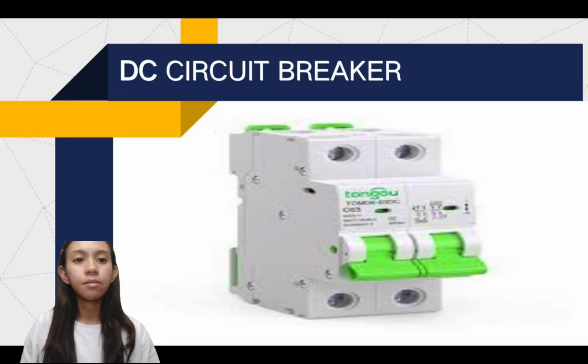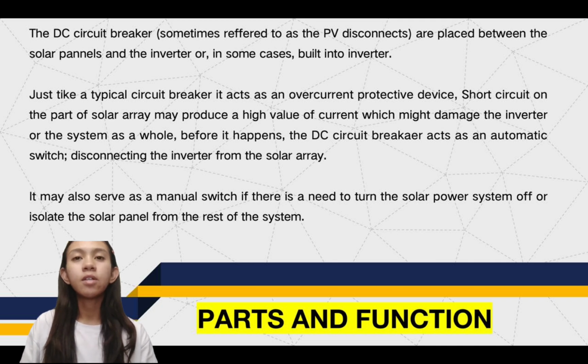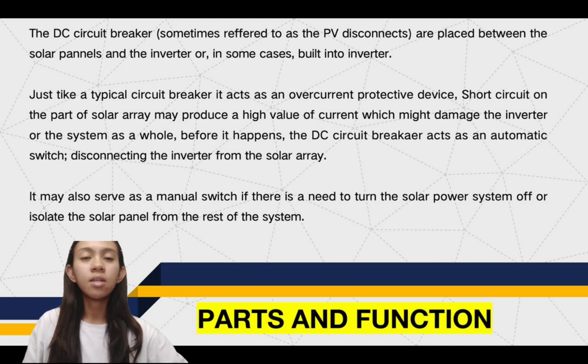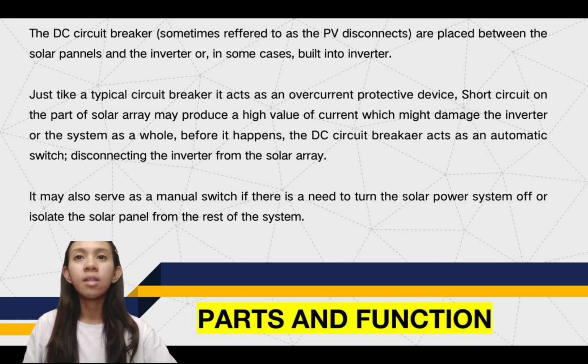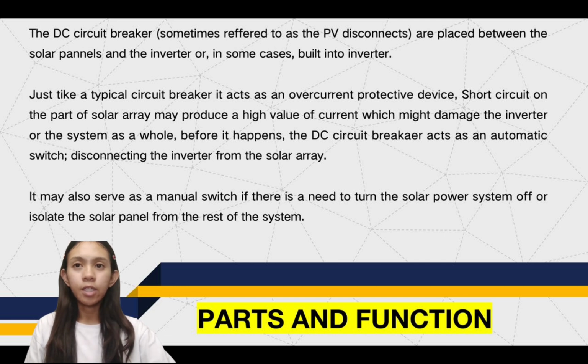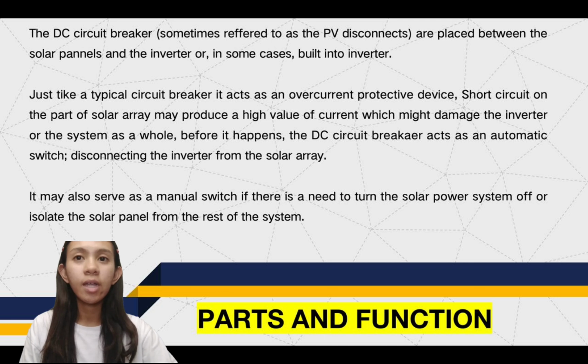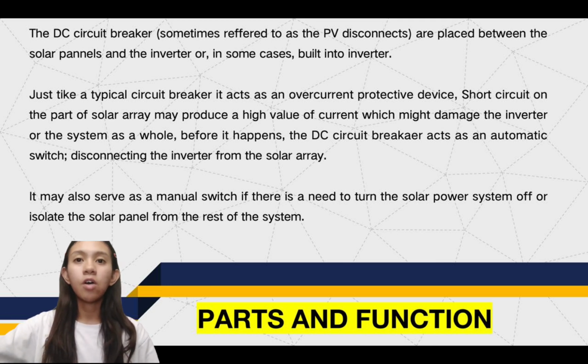DC circuit breaker. So, DC circuit breakers, sometimes referred to as PV disconnects, are placed between the solar panels and the inverter, or in some cases built into the inverter. Just like a typical circuit breaker, it acts as an overcurrent protective device. A short circuit on the part of a solar array may produce a high value of current which might damage the inverter or the system as a whole. Before it happens, the DC circuit breaker acts as an automatic switch disconnecting the inverter from the solar array. It may also serve as a manual switch if there is a need to turn the solar power system off or isolate the solar panel from the rest of the system.